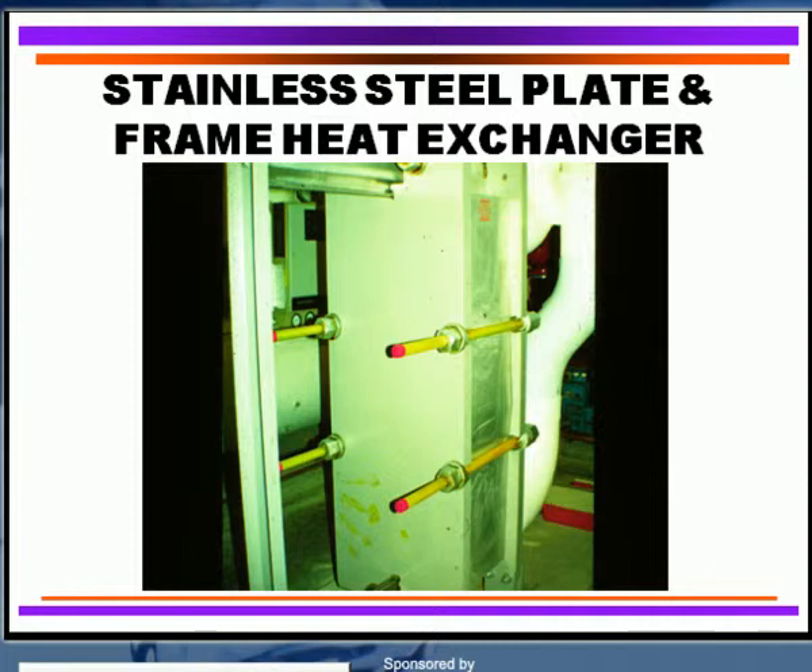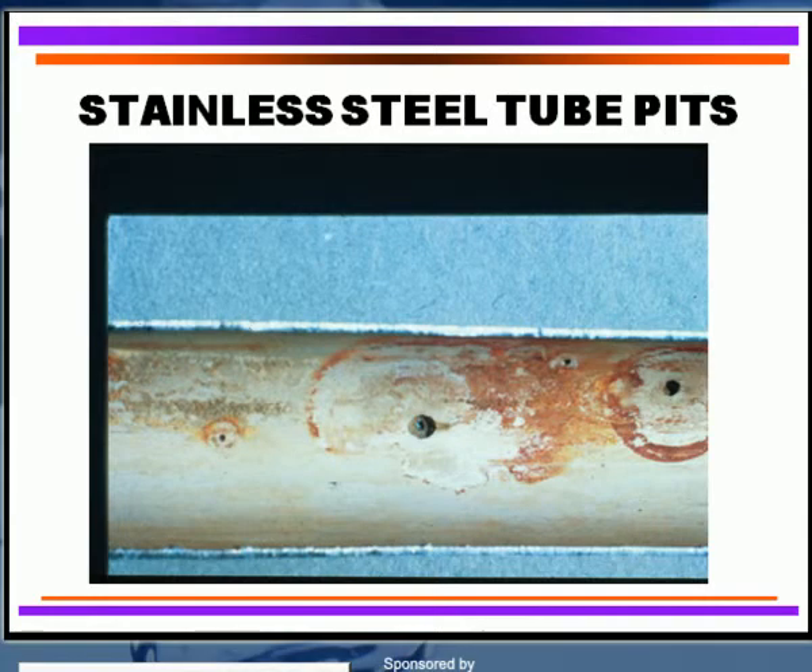Here's an example of a pitting attack on stainless steel tubing. This particular attack has occurred in a matter of 72 hours or a little bit longer, and that particular attack was due to sulfate-reducing bacteria. So keep in mind that sulfate-reducing bacteria and high chloride can cause serious pitting attack on stainless steel.